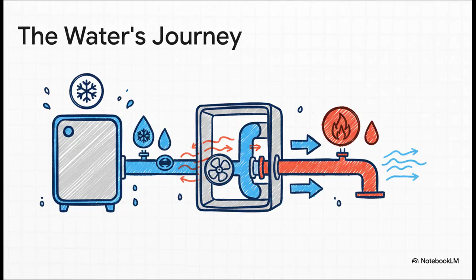So that fresh 6-degree water gets pumped out from the chiller through a whole bunch of insulated pipes. It travels all over the building to those air handling units. Inside those units, warm air from the rooms gets blown across coils filled with this super cold water. The air gets nice and cool, and in the process, the water does its job. It absorbs the heat, warming up to maybe 12 degrees Celsius. This warmer water then makes the trip all the way back to the chiller to drop off its heat, get chilled down again, and head back out. It's a non-stop cycle, 24/7.